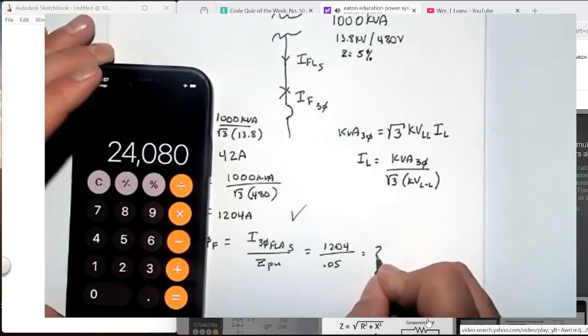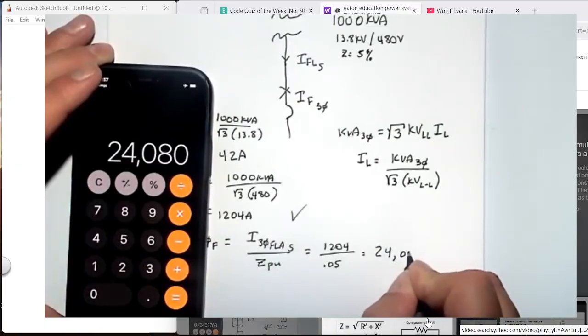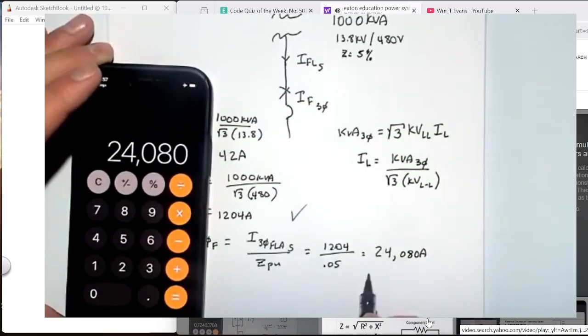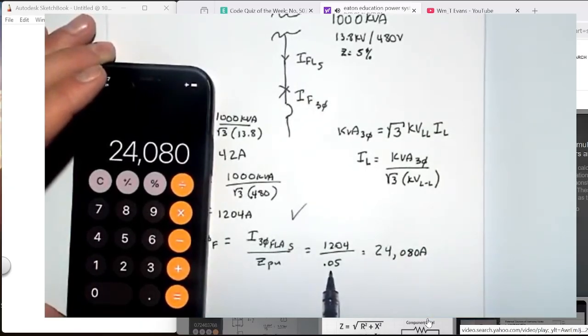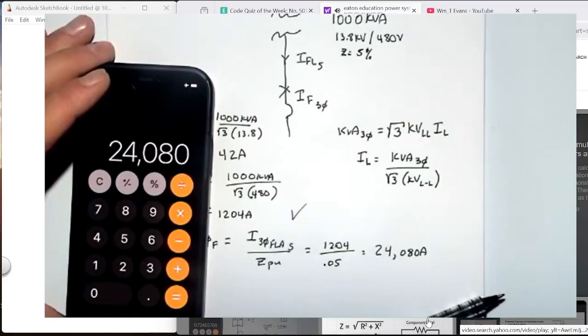1204 divided by 0.05, and we get about 24,080 amps, or 24 kA. That's our fault current. Since the impedance is 5% or 0.05, this number is 20 times the full load amps. Again, interesting things to think about. 1 over 0.05 is a ratio of 1 to 20, so the ratio of the fault current to the full load amps is 20 times. And that's how we're going to size our kA rating for our breakers. So those are just a few of the things that we want to think about.